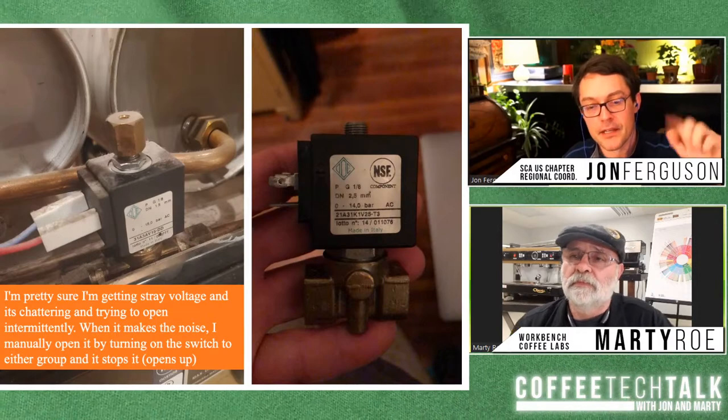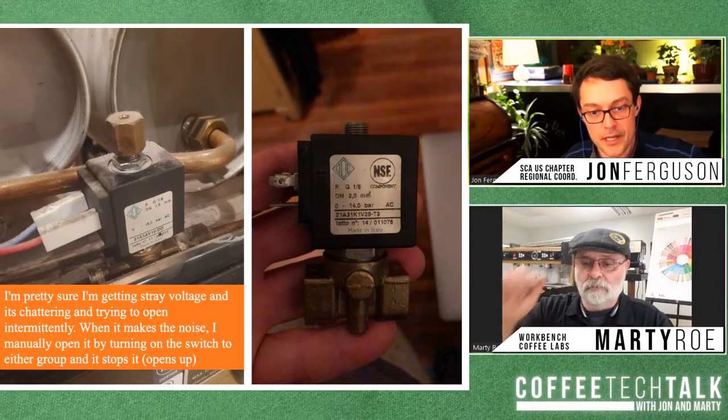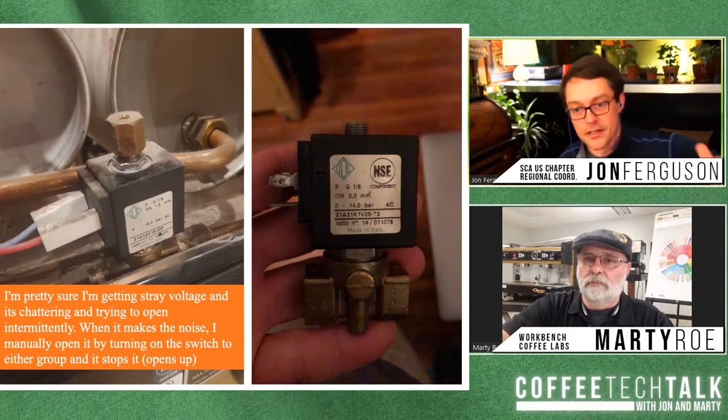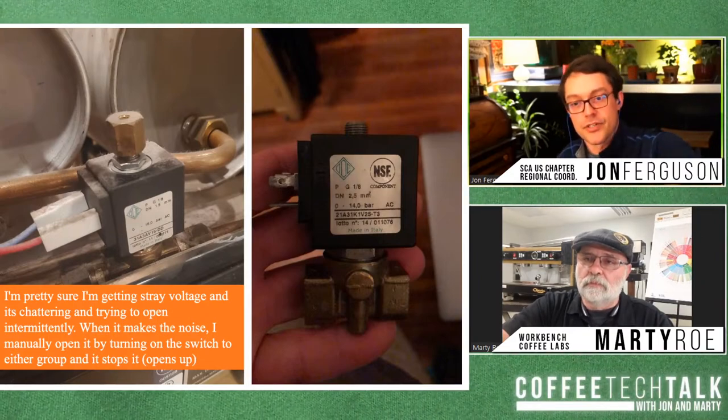This is what he said: I'm pretty sure I'm getting stray voltage, and it's chattering and trying to open intermittently. When it makes the noise, I manually open it by turning on the switch to either group, and it stops, it opens up. He's like, this is probably what it is. This looks like a fill valve.